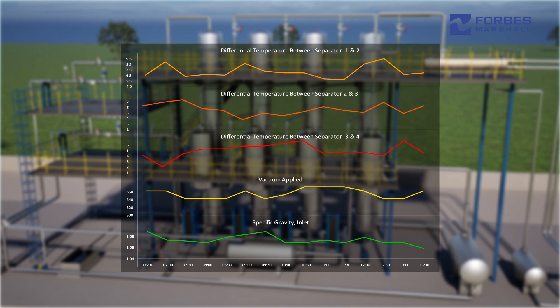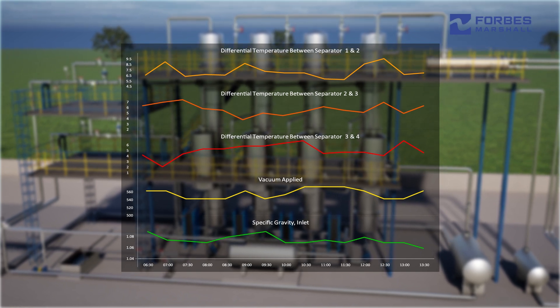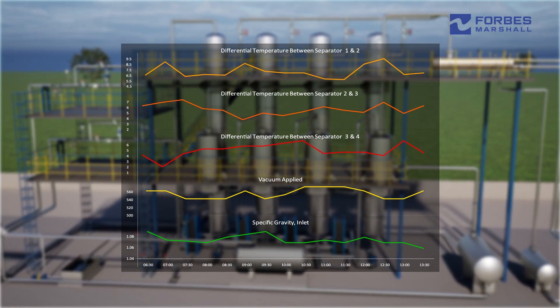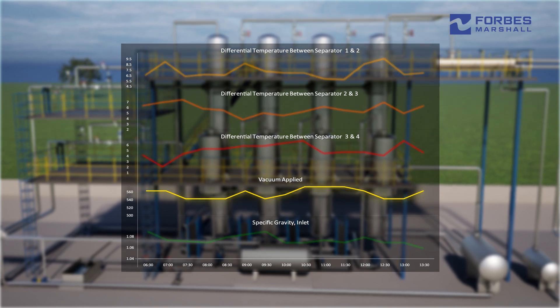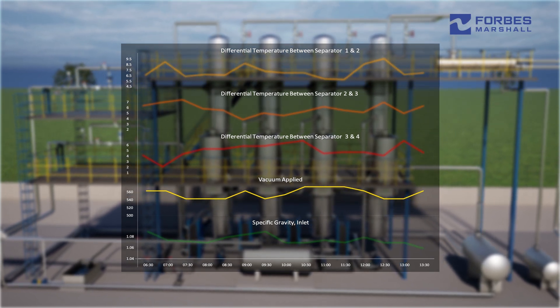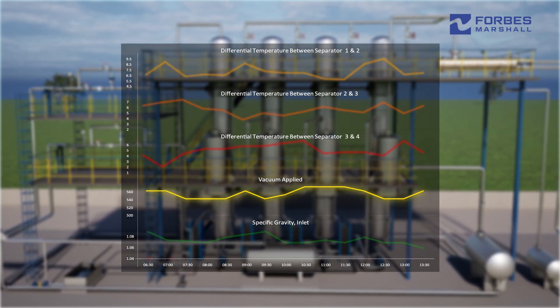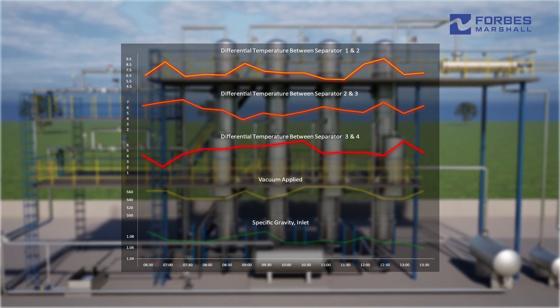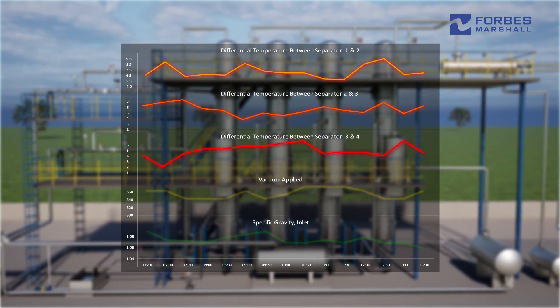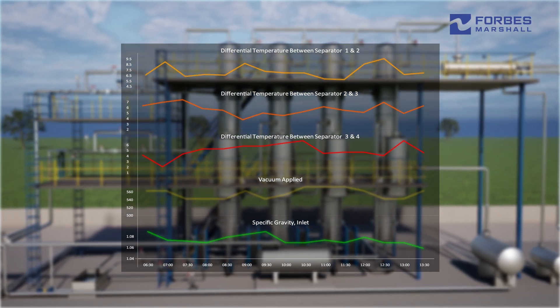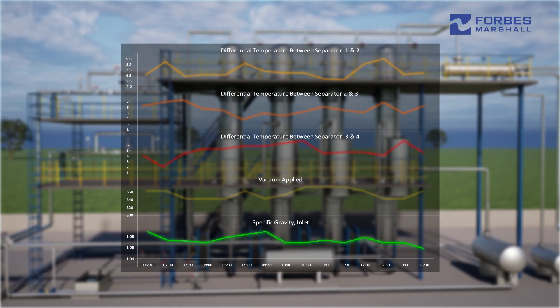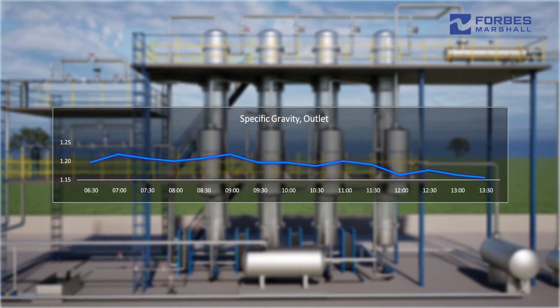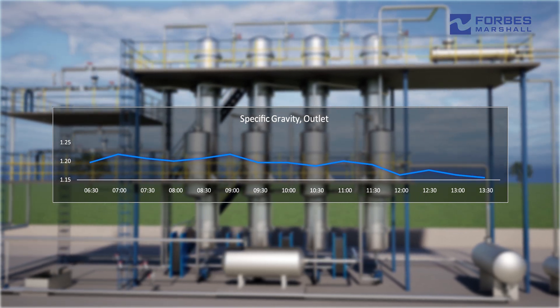During actual operations, significant variations in parameters besides steam pressure can be observed across multiple effect evaporators. This includes variations in vacuum, which affects the boiling point and results in variations in evaporation, variations in differential temperatures between effects, and variations in inlet feed flow and concentration. These ultimately cause variations in outlet concentration.